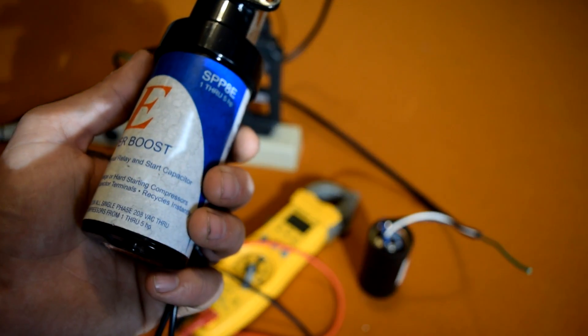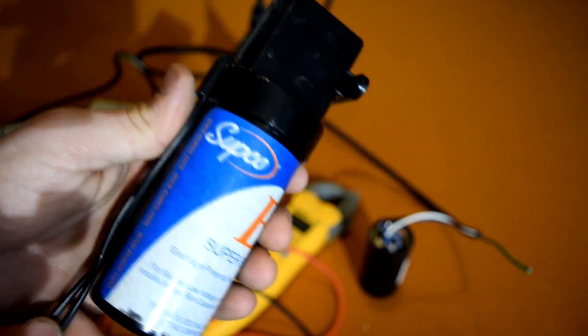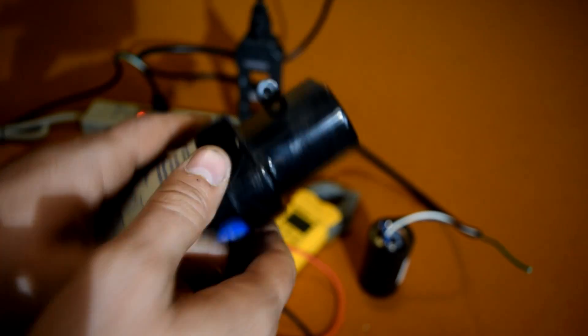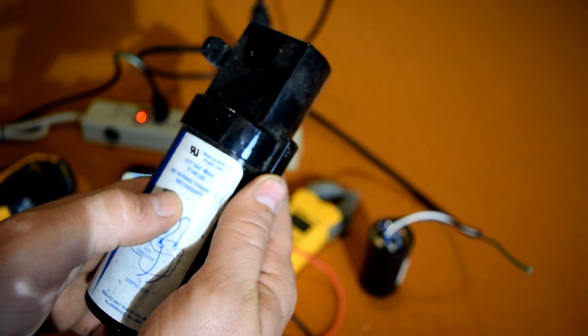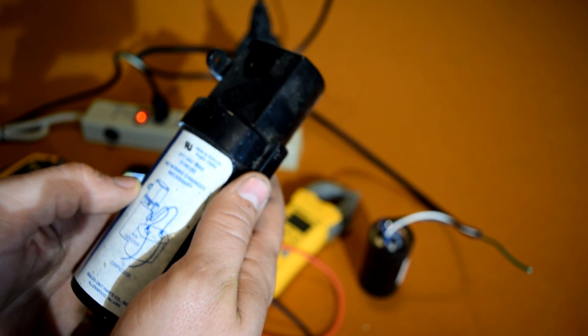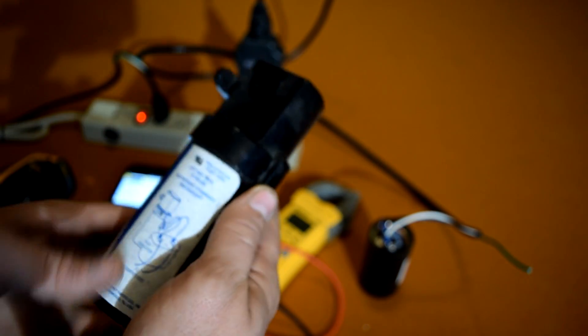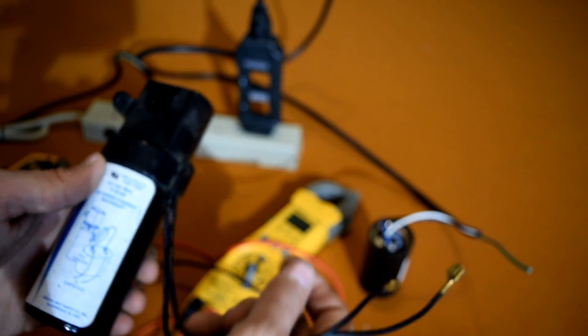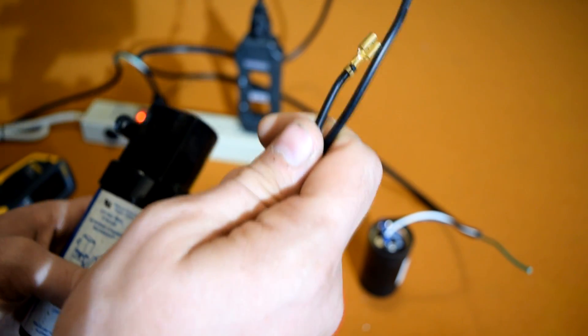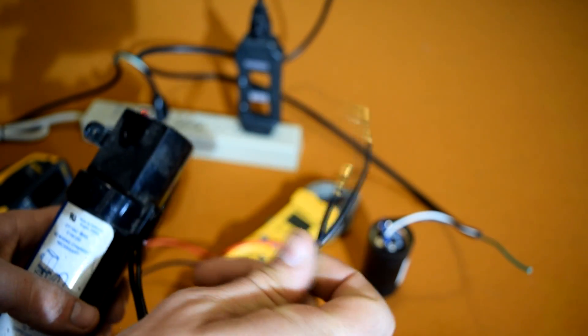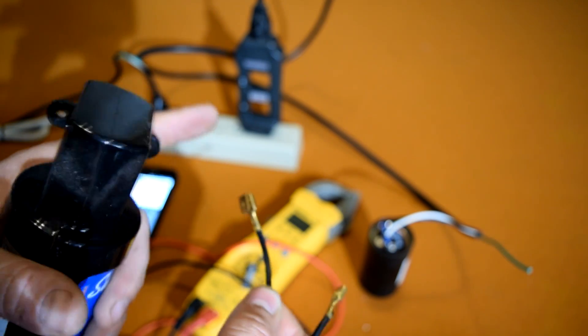This is designed for a heat pump, designed to plug into a 230 voltage alternating current circuit. No wiring changes are necessary to this type of system. If I was to connect my system to this, what I've got to do is plug these two terminals into the run, the hermetic for the compressor, and the common. Your hermetic would go here and common would go here.